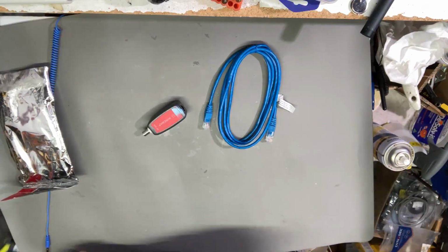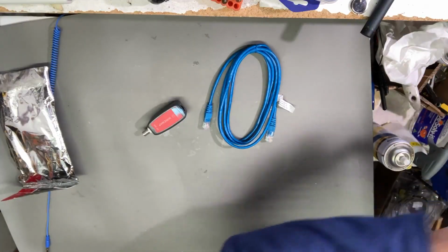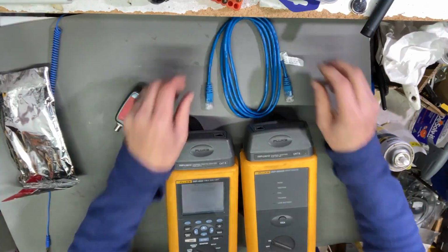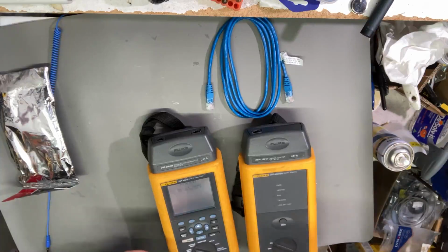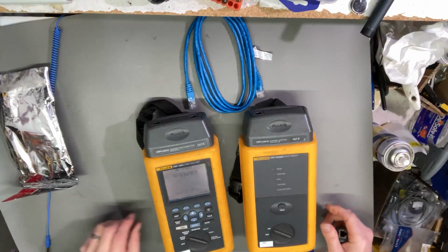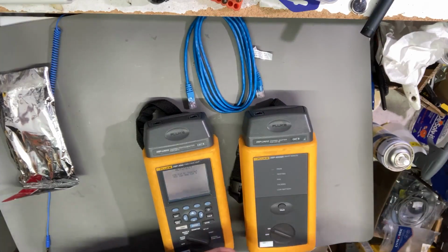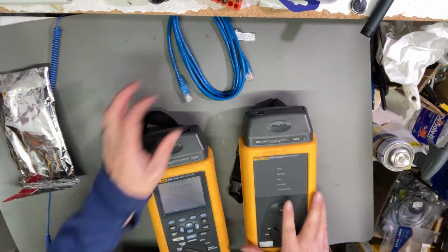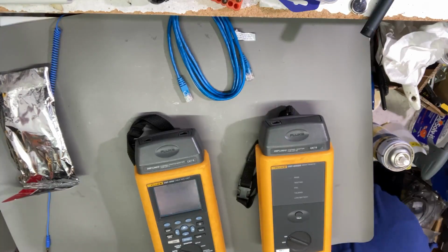This is where the cable analysis is handy, because the cable analyzer goes a bit further than that. It's going to actually send signals down the cable and see if they appear on other pairs of the cable. If that happened, that would be crosstalk, and there is always crosstalk, but it's just whether that exceeds the standards that are set for each cable standard.